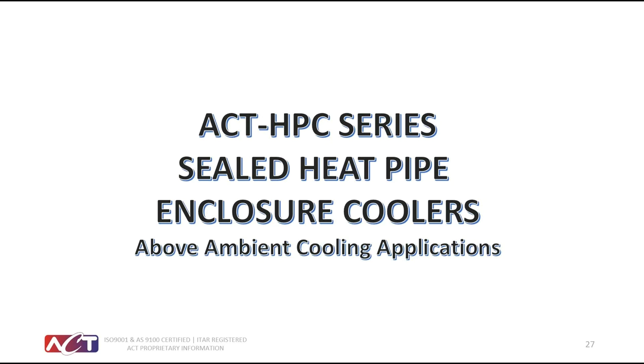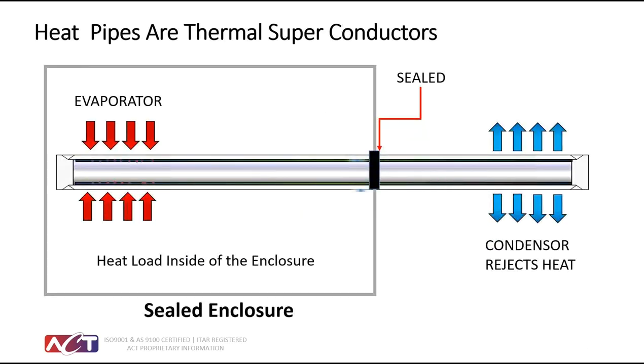The next product we'll talk about is one of the core technologies here at Advanced Cooling Technologies, the Heat Pipe Cooler Series. And essentially, the heat pipe coolers use a number of these heat pipes that are bonded with fins. And so on the inside of the enclosure, the heat from the inside of the cabinet causes the working fluid inside of these heat pipes to boil, and they go to a vapor. And as they go to the outer cabinet, the vapor condenses and then travels back by gravity. And this heat exchange of going from a liquid to a vapor becomes 1,000 times better conductor than a solid piece of copper. So we're able to very effectively and efficiently transfer the heat load from the inside of the enclosure to the outside. And again, we have fans blowing over the inside of the enclosure and fans blowing over the outside of the enclosure.